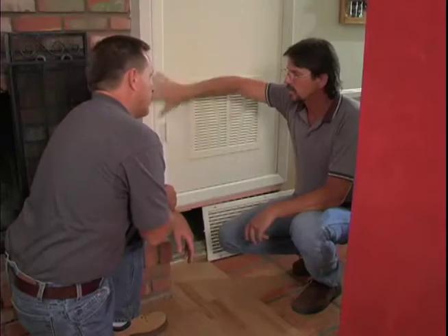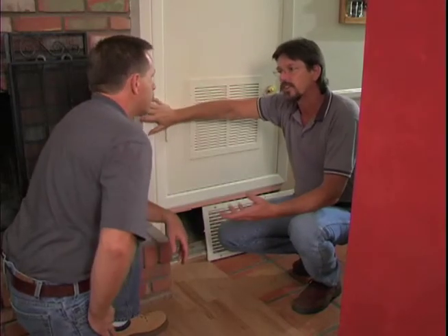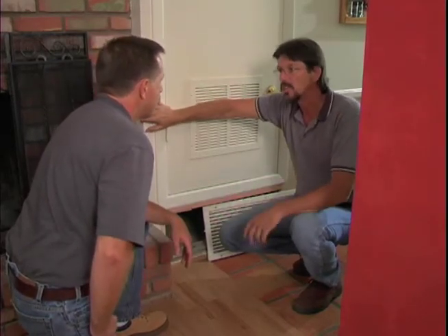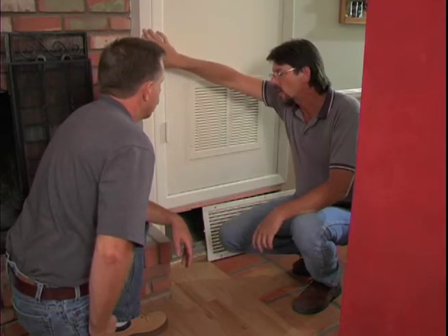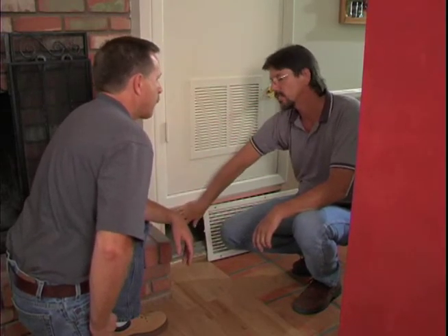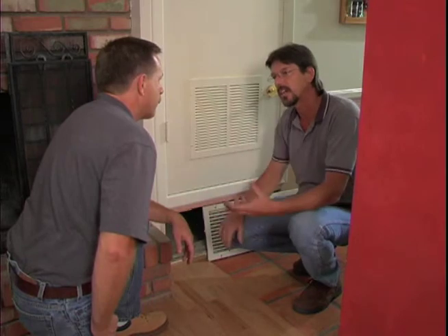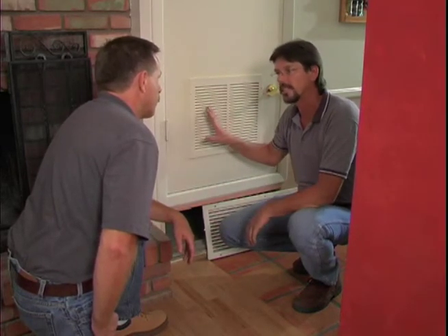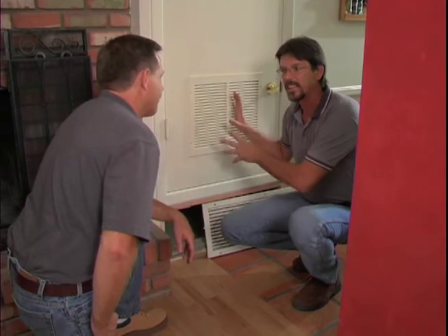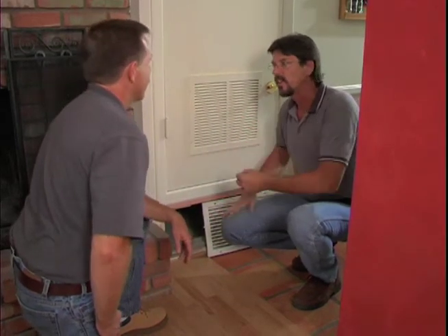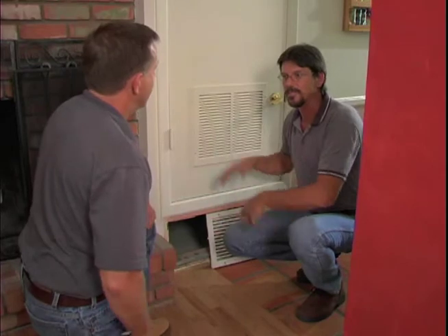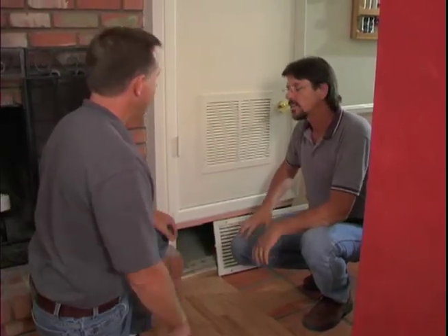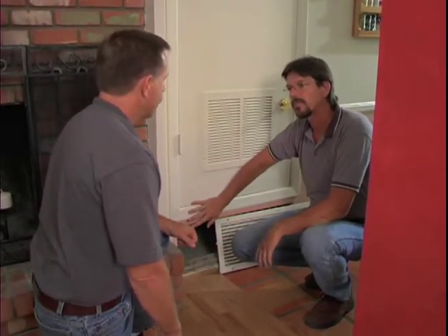I see. So when this air handler is running, when you're trying to air condition your home and keep it at 78 degrees in the middle of the summer, you're pulling 160 plus degree air right into the return system itself, and you're mixing 160 degree air into the 78 degree air and trying to cool it. So instead of the air handler being able to cool your home efficiently, it's completely out of whack. Is this a pretty common problem? It's a really common problem for this style platform for the age of the home.